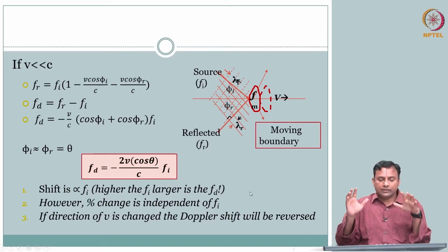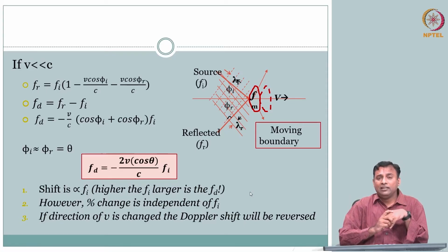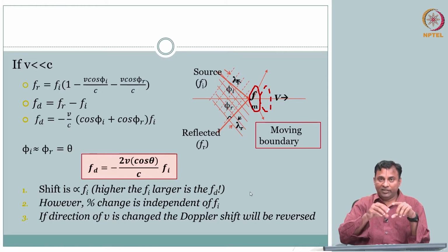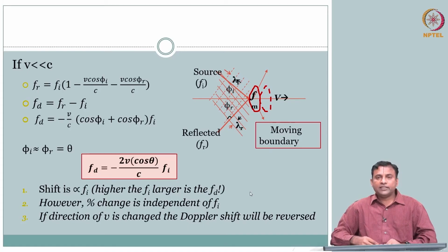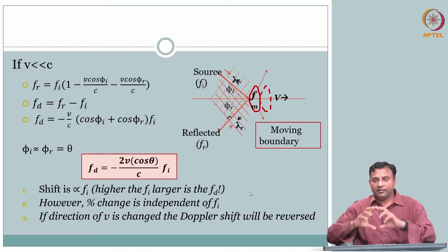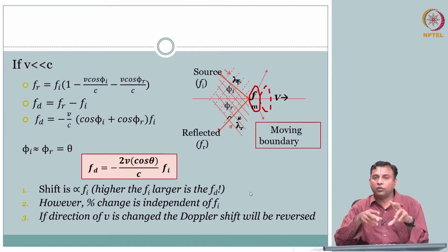From a simple physics point of view, this is the Doppler principle. But when we actually exploit this for imaging, there are a bunch of trade-offs involved, because the whole idea is you want to estimate the velocity, and preferably place the blood inside the vessel and register it against the structural image of the organ. So where is that vessel? Inside the vessel something is flowing. So typically you have to do the imaging ultrasound.